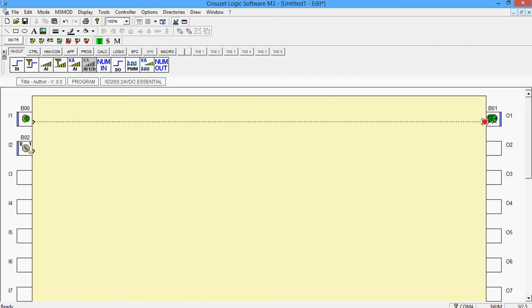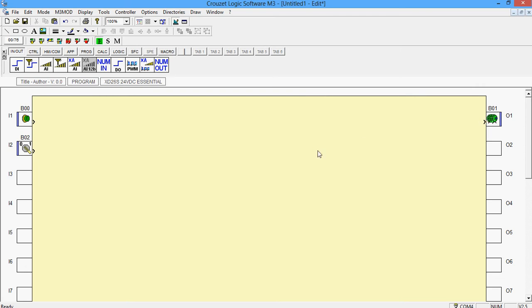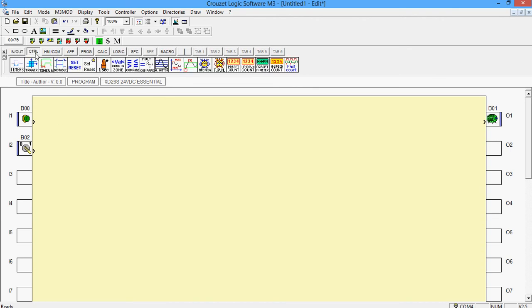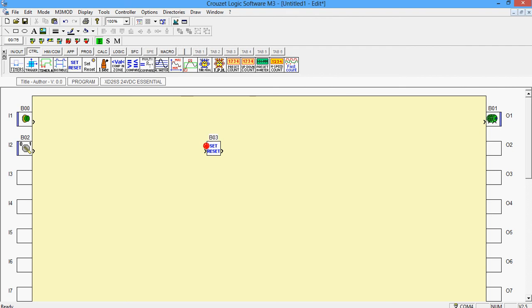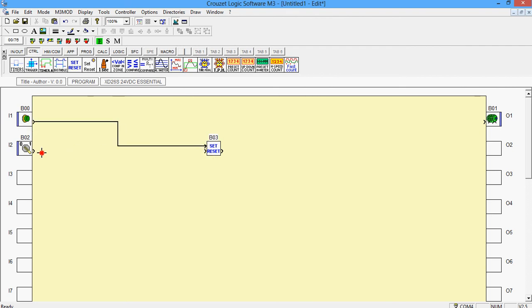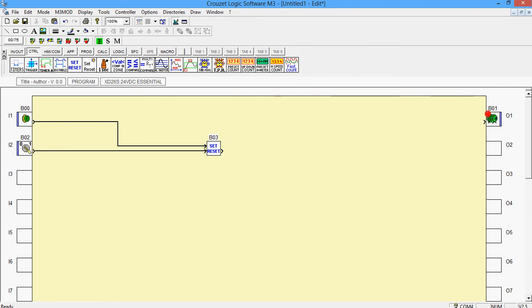Which means if I press start, the motor will start. If I press the start button again, the motor is going to stop. So that shouldn't happen here. I'm using something called set reset. By using this, I'm connecting the set to the start button and the reset to the stop button, and I'm giving the output to the motor.